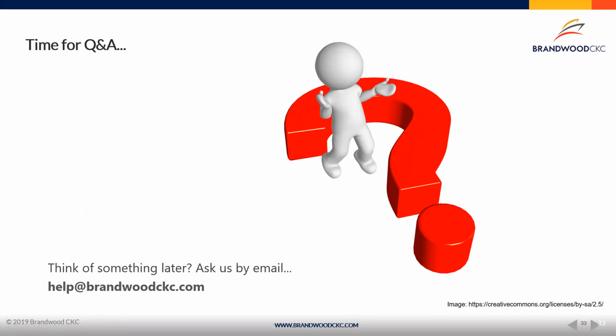The first one I had was a question that came in before the webinar. Effectively, the question was asked: does ISO 13485 production require, or do all companies require, production risk management? And ultimately, you need to be able to show risk management for the production side of things.